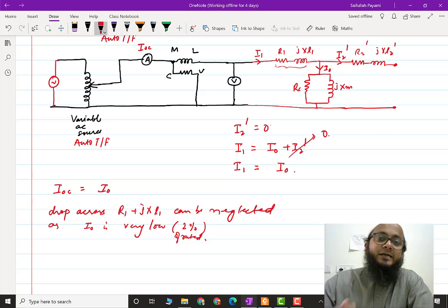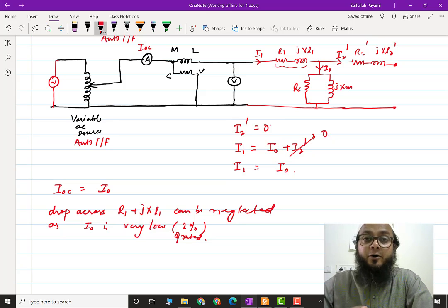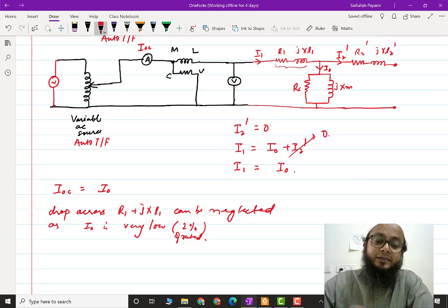For the low voltage side, that is lower. Even the leakage reactance, we have represented by an inductor, which depends upon the square of the number of turns. So for the low voltage side, this number of turns is lower. So we can directly neglect the voltage drop across these series branch parameters. So what we can say is, we have just these shunt branch parameters there.